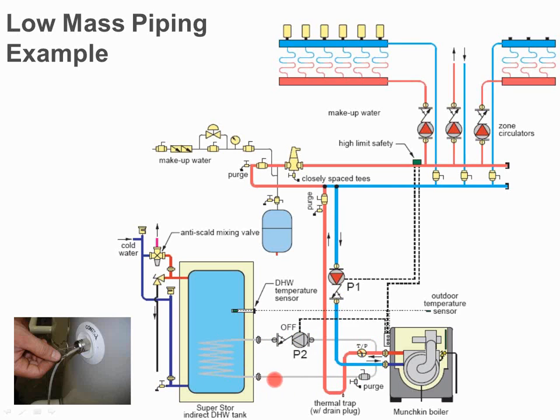Normally these tanks take maybe 10 to 15 minutes to do that. I've even seen 119 gallon indirects heat up off a system in 20 minutes from a cold dead start. We brought 40 degree water into it and jacked it up to like 130, 140. So they're very, very fast. They're very efficient because you're looking at very cold water temperature. You're back to that boiler, it's seeing those temperatures, it's generating the heat, and you got a lot of mass. You got a lot of power in that boiler. So it works very, very well.